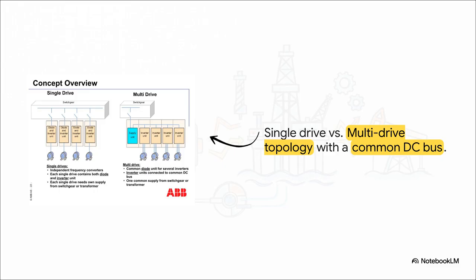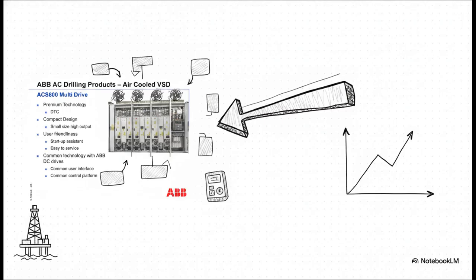This is a total game changer. It means a way more compact footprint, fewer components, less cabling, and you can even share braking resources across several drives. This brings us to the actual hardware: the ACS 800 air-cooled multi-drive. It's exactly that shared DC bus architecture we just talked about, productized into a highly compact, premium air-cooled design. You get a ton of output from a really small footprint, all while sharing a common user interface and control platform.